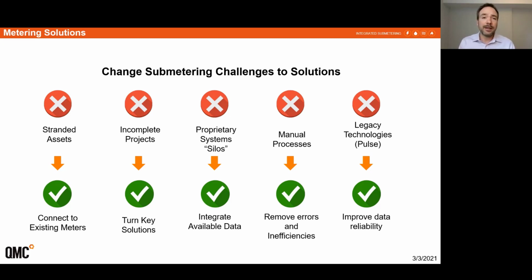And lastly, if you have legacy systems in place, these are often older meters that are really relying on pulse outputs. Almost all meter manufacturers make a meter that gives a pulse output. But the problem with pulses is they don't give us great reliable data. You're essentially getting a pulse per liter consumed or per kilowatt hour. And if we lose connection to that system, briefly even, the meter register itself will never line up with the data that we're seeing on the system, even once a connection is remade with the meter. So we're aiming to move all of the metering systems we come across into what we call register reads. So the data we're receiving is the same as the visual display on the meter. And that way there's never going to be a discrepancy between what the automated system or billing system is seeing and what the meter itself is showing.